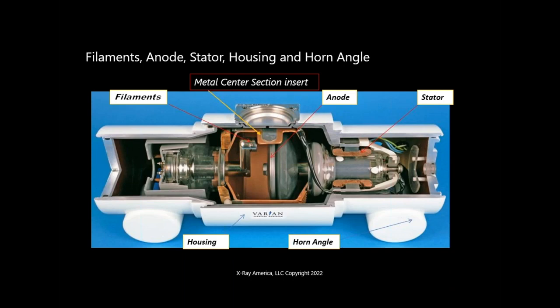That's the difference between reprocessing used oil and using new oil, because dielectric strength has such a big purpose, especially with diagnostic tubes. It's sealed, and it insulates against your housing. So if you have low dielectric strength or you just use oil out of a barrel, that's going to break down quicker and you're going to have arcing to the housing. Versus the anode ground, where you go directly onto the insert itself. When they put the high voltage cable in there, you go right into the insert. That's why that technology is so sophisticated compared to your typical rotating or diagnostic tube. So keep that in mind: this is how all these different factors play into the lifespan of your tube.